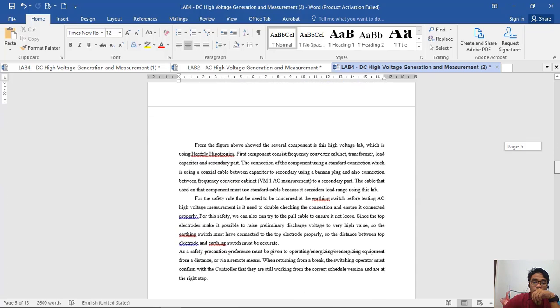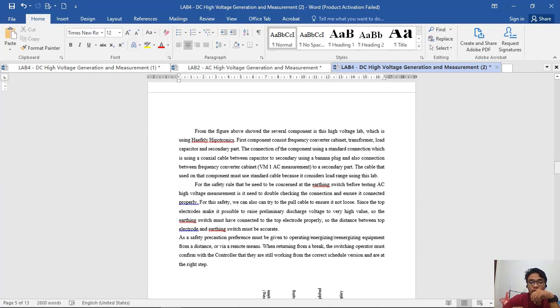And then we go to the safety rule that we need to be concerned about at the earthing switch before testing a DC high voltage measurement. So we have to double check the connection and ensure it is connected properly. As we know, in this lab the earthing should be below 5 ohm. So for safety, we can also try to pull the cable to ensure it is not loose.